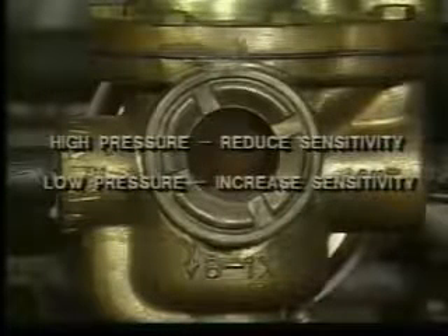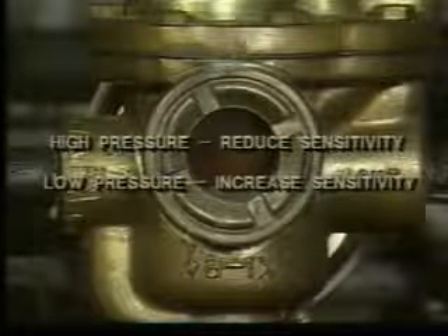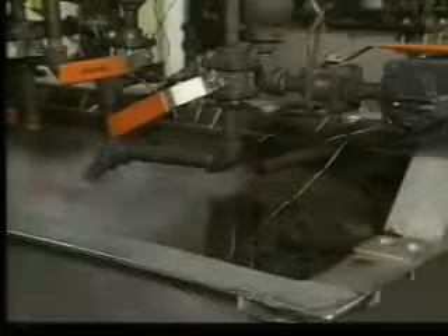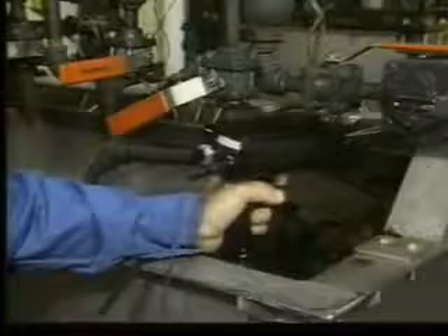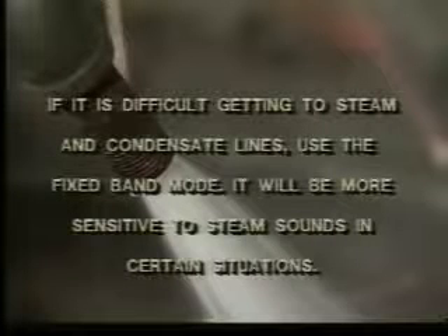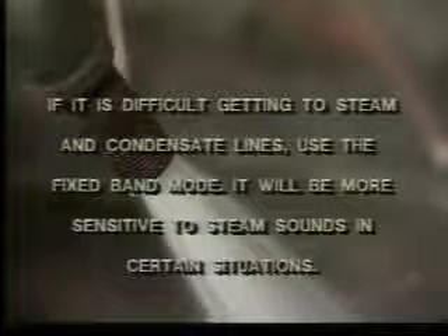In a high-pressure system, you will reduce the sensitivity more than you would in a low-pressure environment where the higher sensitivity is needed. If it is difficult to distinguish between the sounds of condensate and steam, listen to a steam line. Then listen to a condensate line. If it is difficult getting to steam and condensate lines, try using the fixed band mode. It will be more sensitive to steam sounds in certain situations.